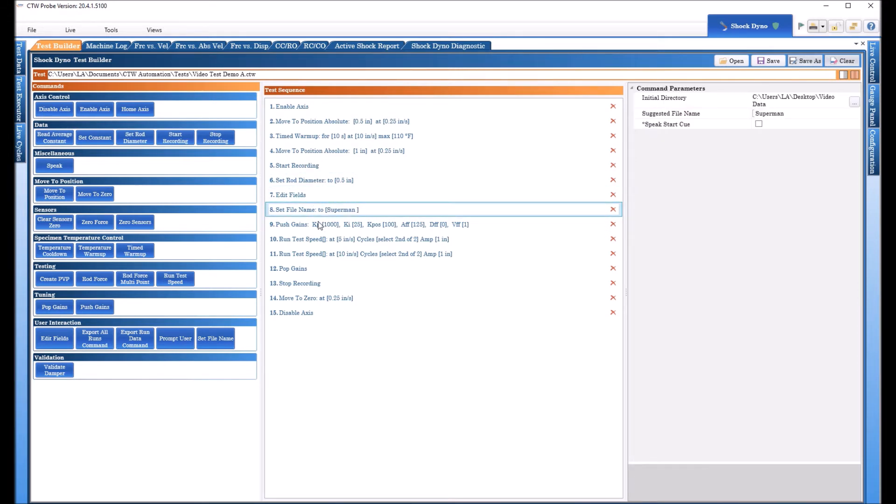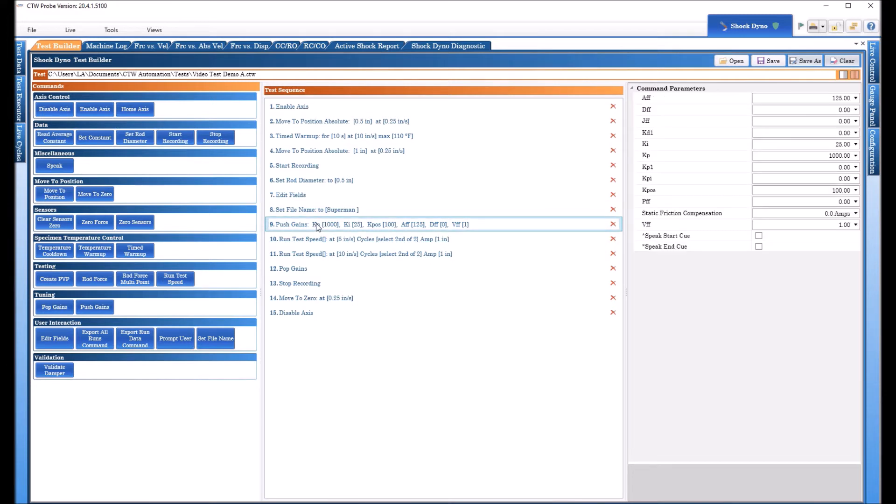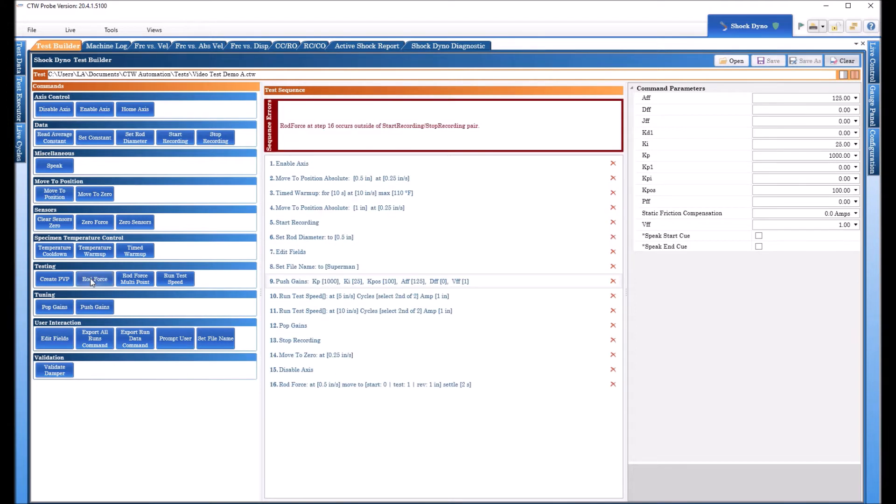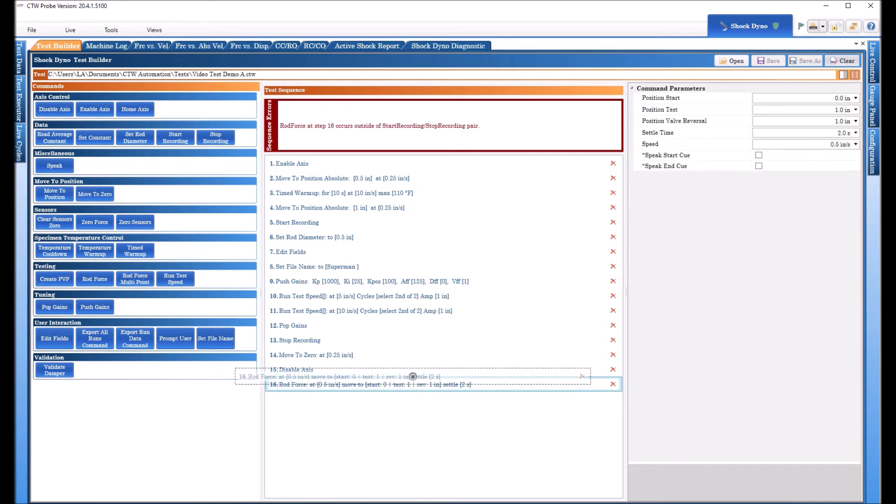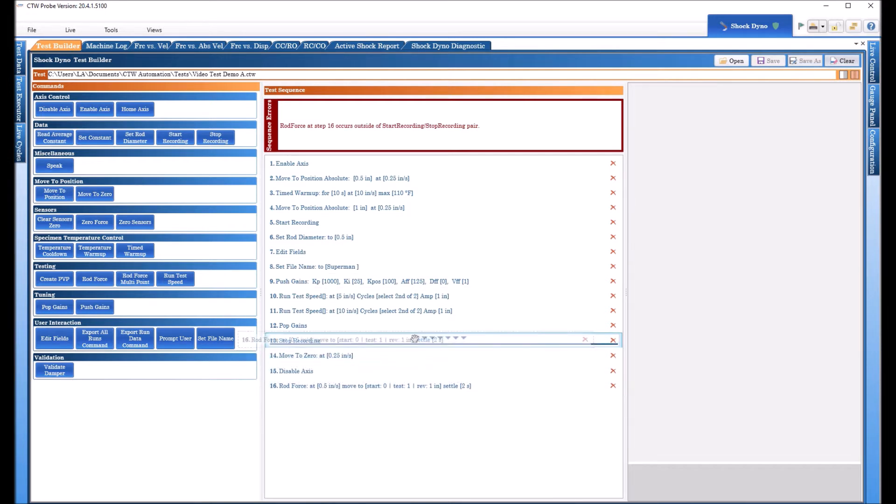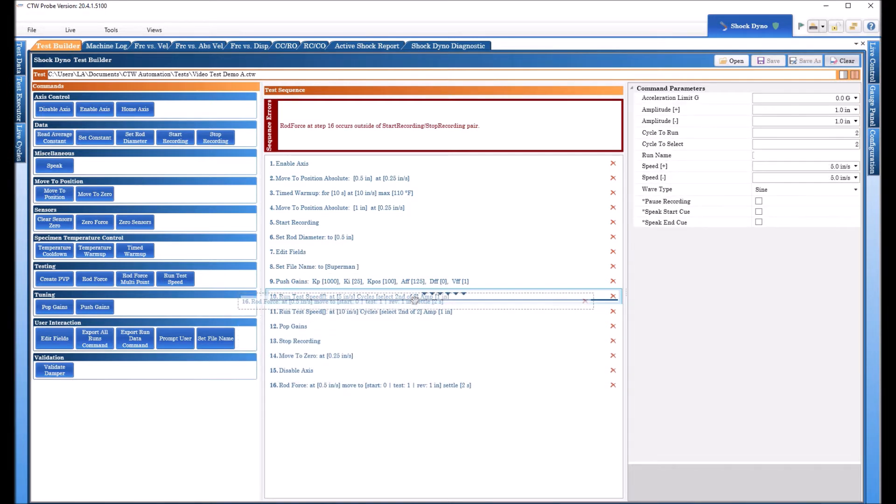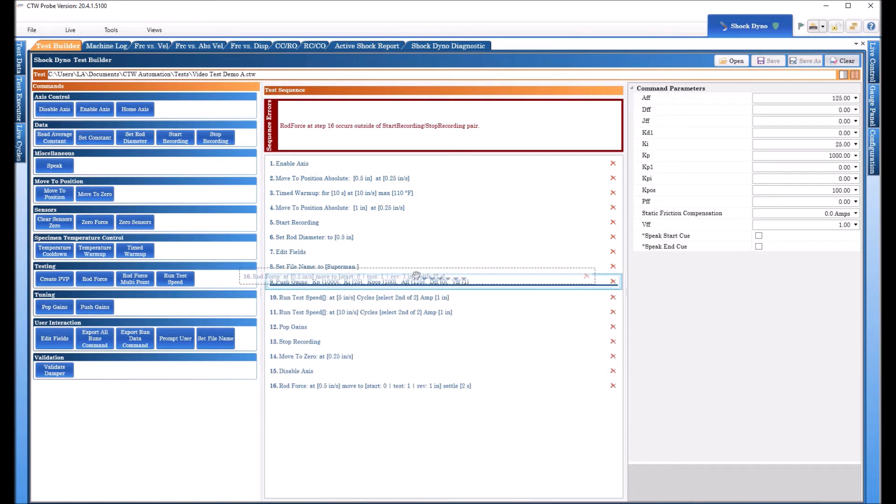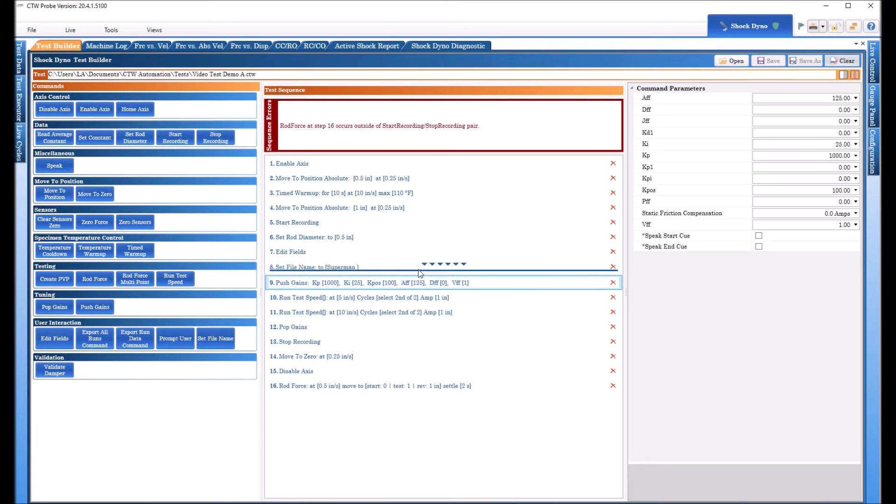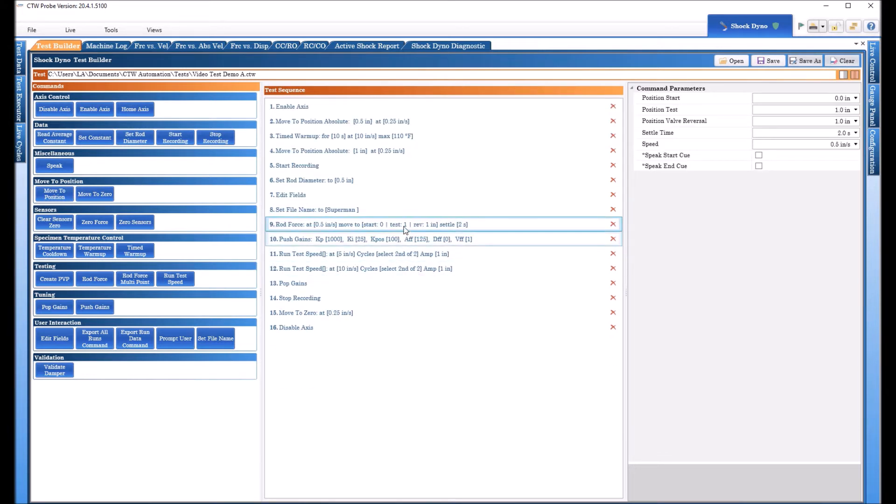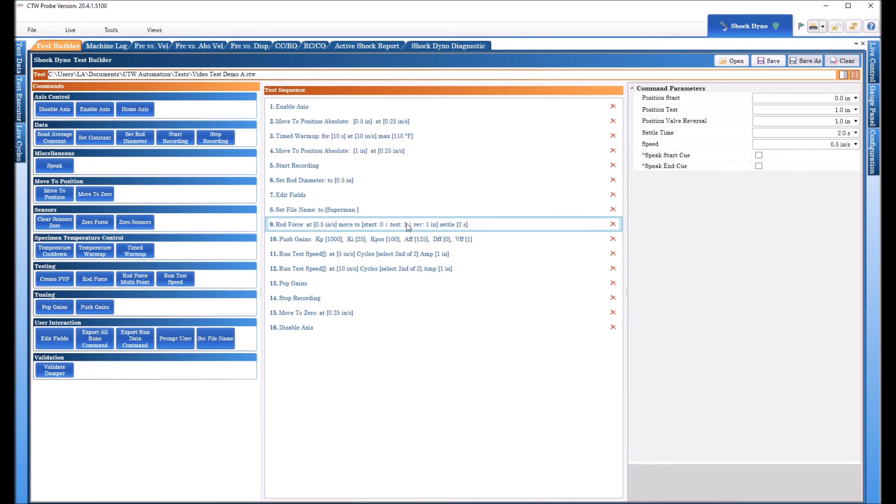Now in the past we did this push gain and before that we're going to add another command that I hope everybody uses, Rod Force. And in the next video we're going to show you the multipoint. The Rod Force is basically a way to measure any internal pressure trying to push that shaft out of the damper so that we can measure it and then remove it from the data. Because ultimately it's just a spring force.